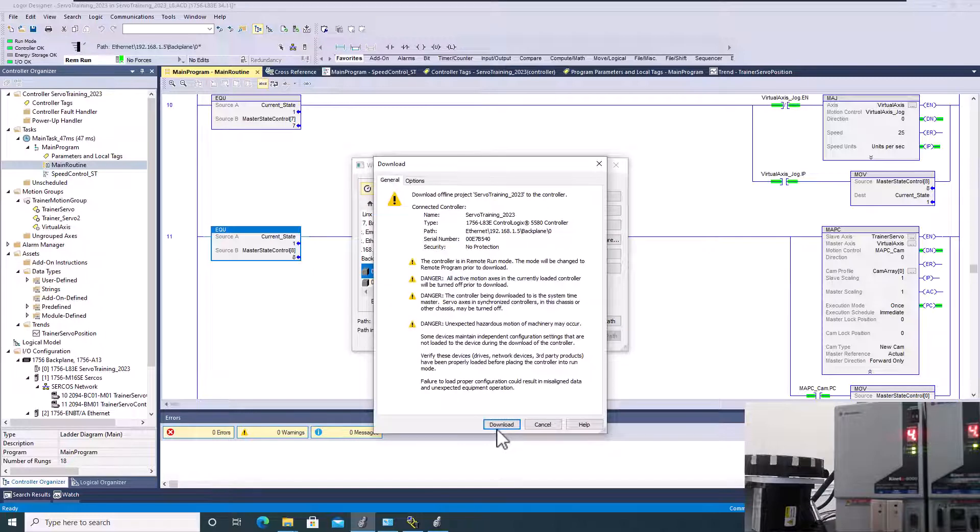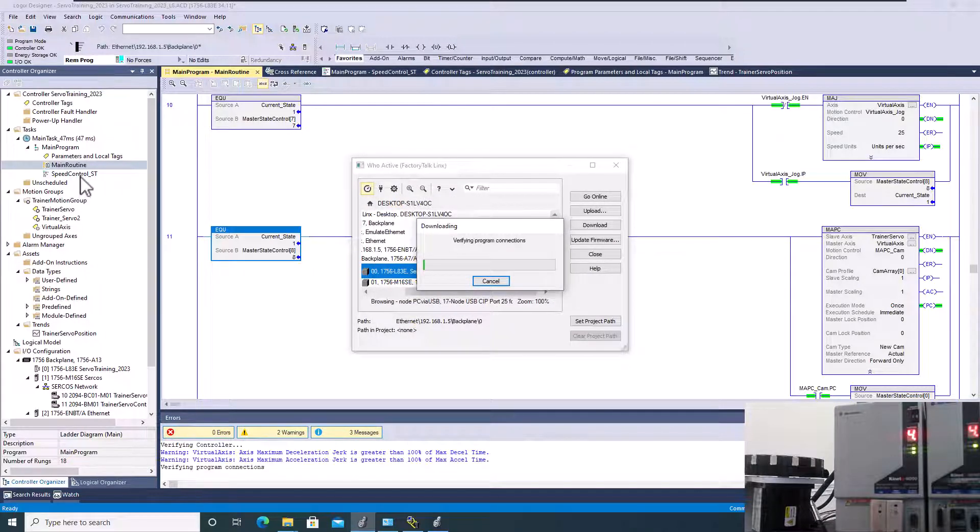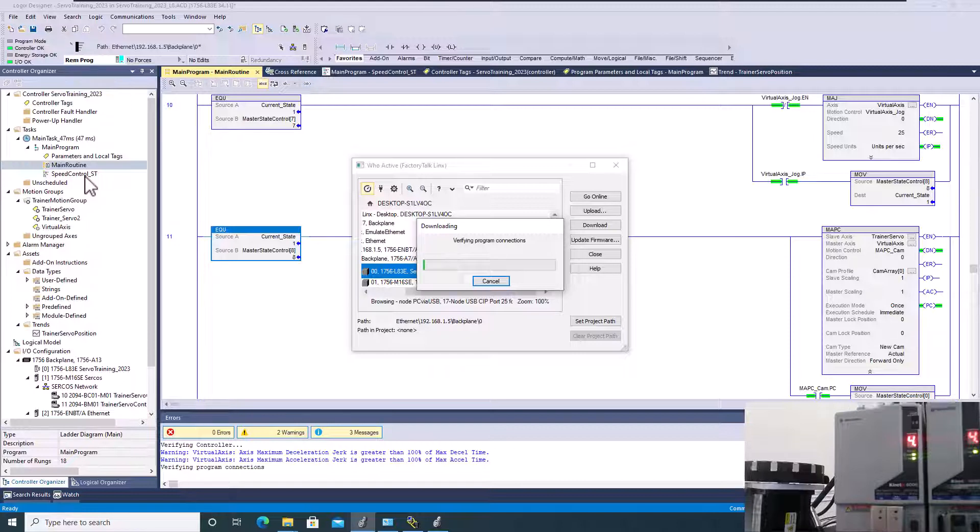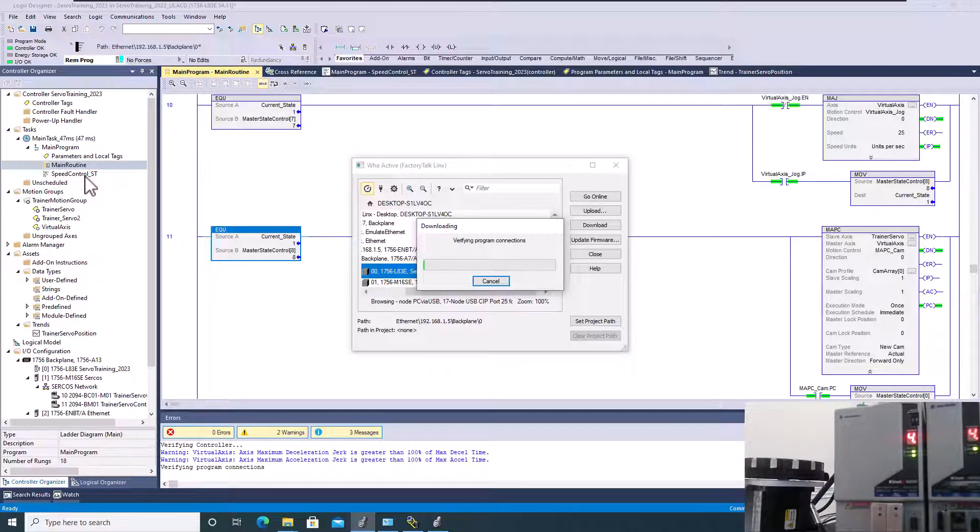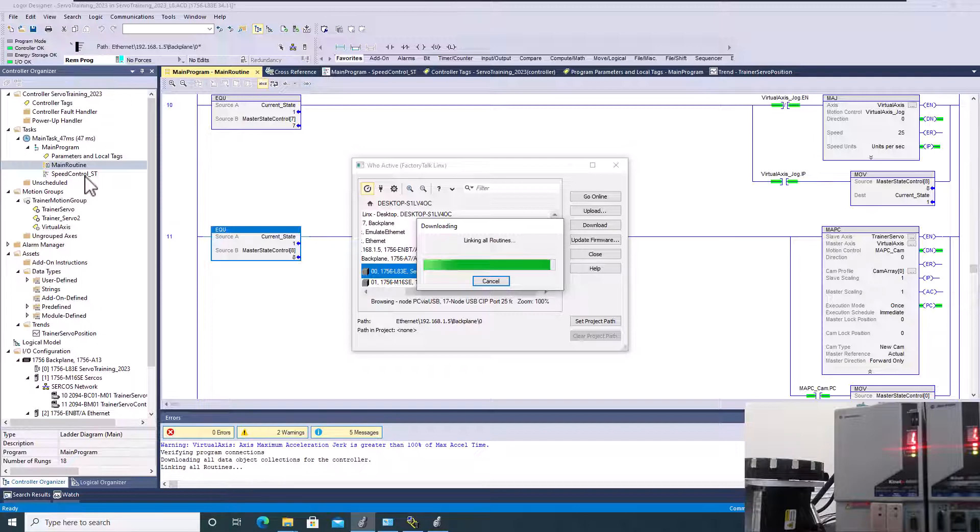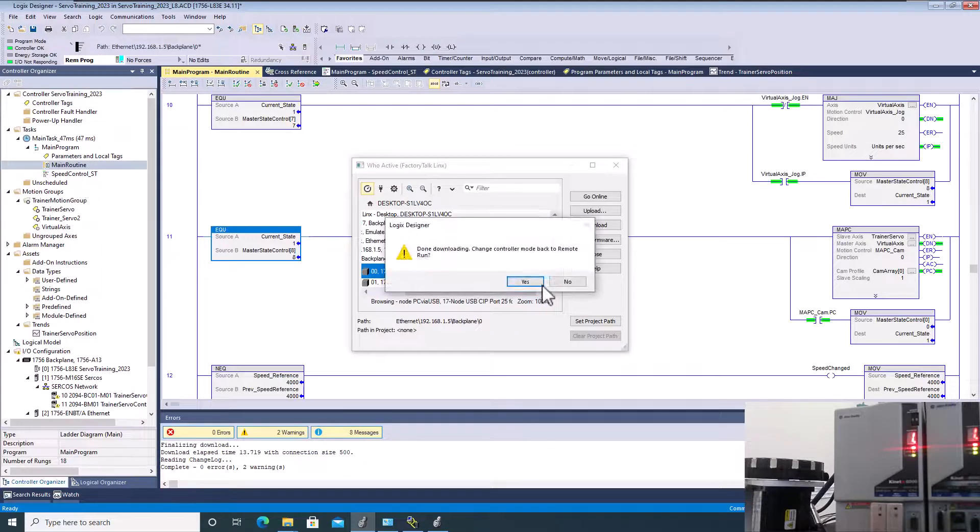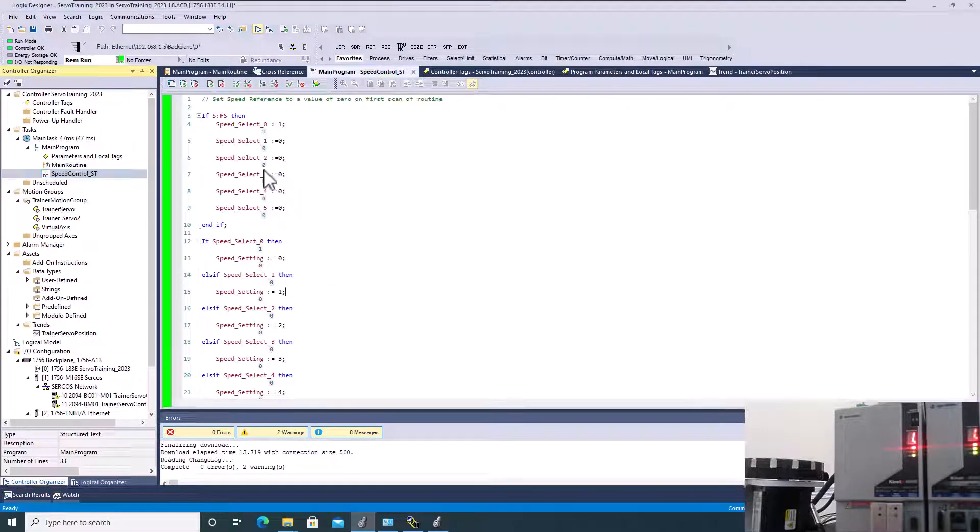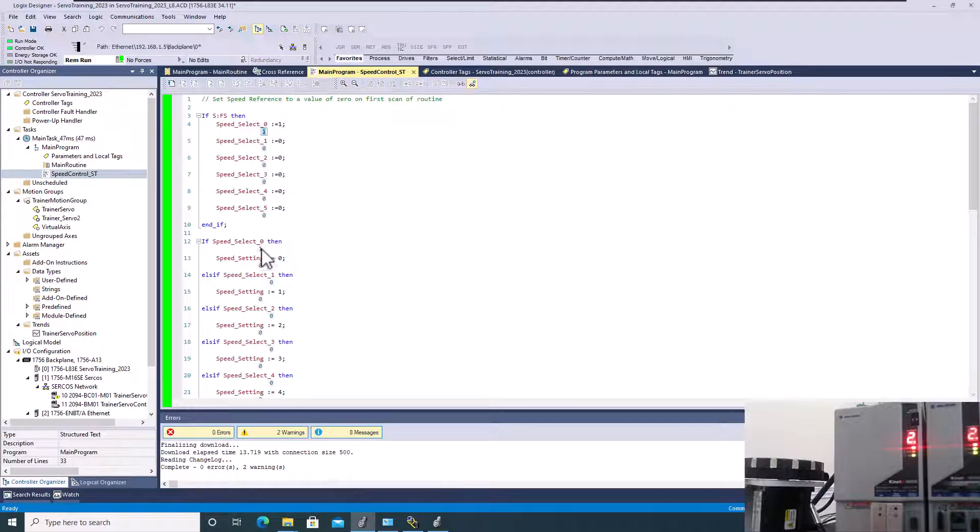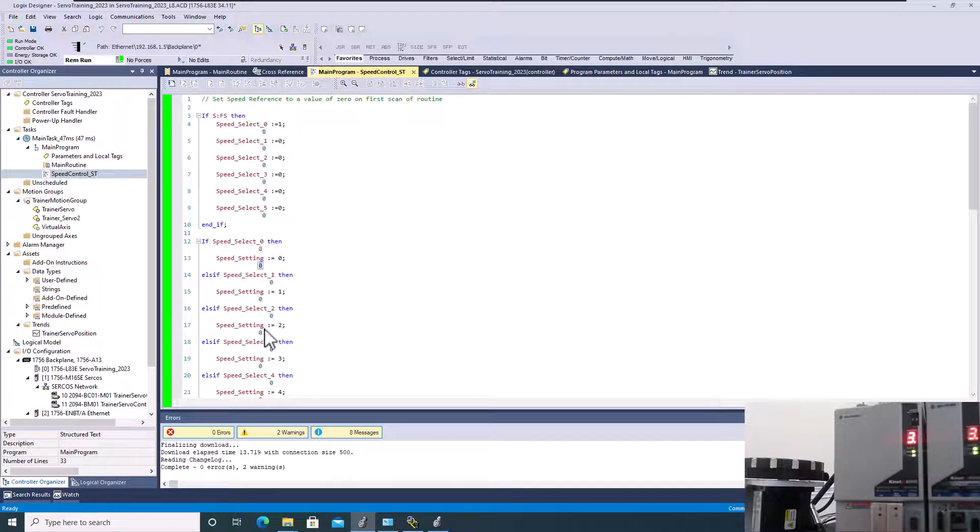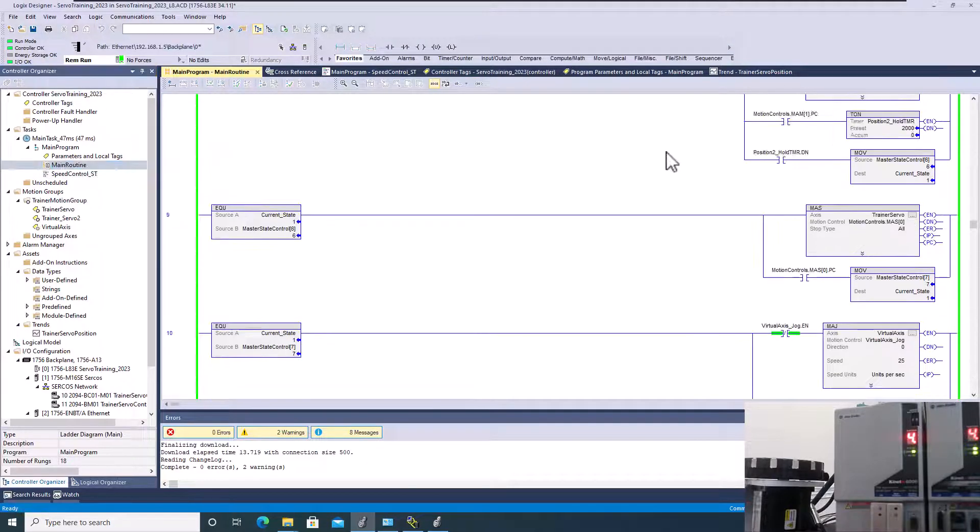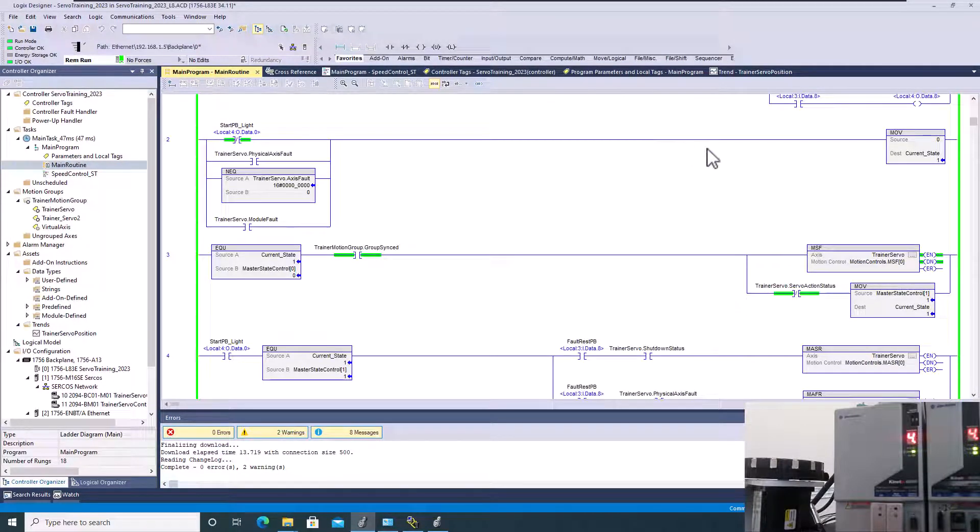And I want you to recall when I download, what I'm going to have to do is being that my speed controls are set to zero off of first scan, and I am downloading, so the first scan bit is triggered off of the actual download process. And that's done basically to keep a safe manner. So if I had my HMI pulled up I could easily select my speed, but in this case I'll just come in and edit this bit. So we'll put this at zero and we'll give it some speed. We'll put this at three or one, speed of three. So let's select that. Let's start our system and see if we fixed our error this time.